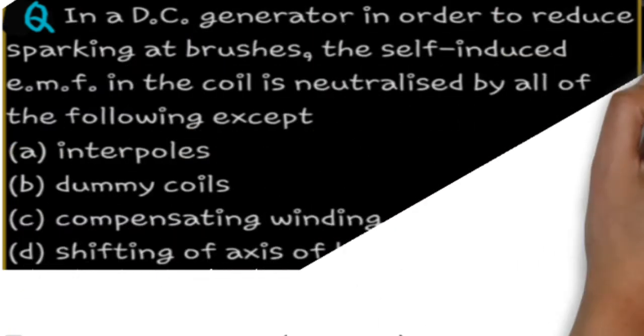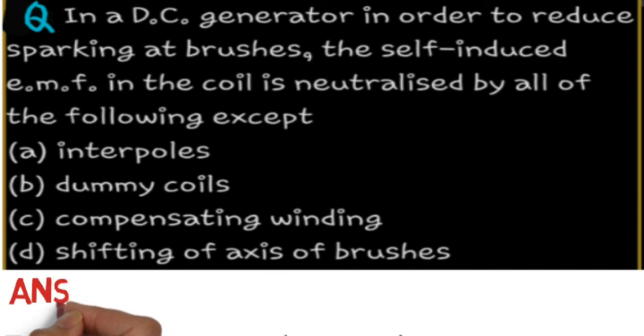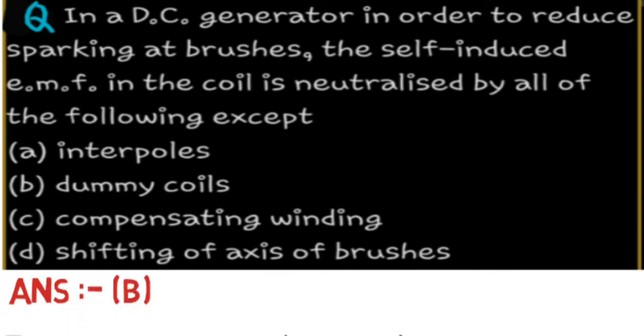MCQ 1: In a DC generator, in order to reduce sparking at brushes, the self-induced EMF in a coil is neutralized by all of the following EXCEPT: (A) interpoles, (B) dummy coils, (C) compensating winding, or (D) shifting of axis of brushes. The answer is B — dummy coils. Interpoles, compensating winding, and shifting of brushes are used to reduce sparking, but dummy coils are used only for mechanical support of the rotor.